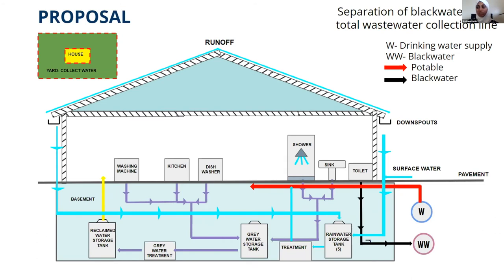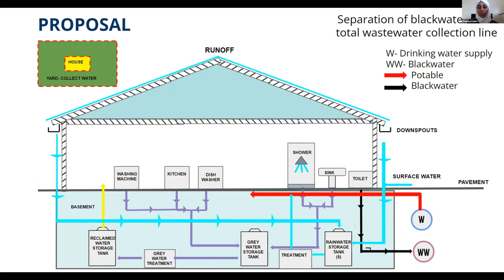For our proposal, we have decided to reuse all graywater for toilet flushing. In addition to this, we would like to collect precipitation from the roof via the gutters, as well as the surrounding surface area, as shown in the illustration and box diagram. In our box diagram, the cyan line represents the roof and gutter collection. The black water line is only receiving from the toilet. The lavender line is the water collected from sinks, showers, dishwashing, and washing machines, which is then treated and pumped back to the toilet for flushing.